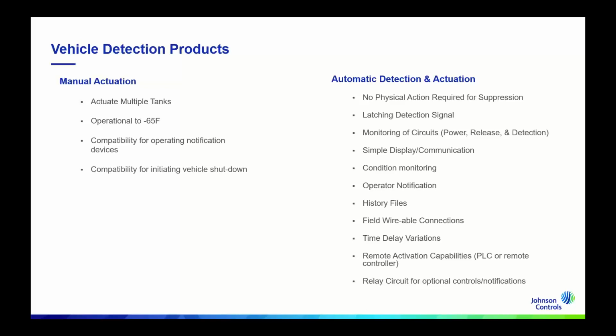In addition to the visual and audible indication to the operator, having the ability to access a history log within the system also provides valuable information about the system and the events that happen. In this case, that history log is basically the picture that can tell you 1,000 words. Automatic detection is critical in order for us to provide that holistic solution that doesn't require manual intervention by a human, right? So that, whether we're there or not, that fire suppression system is going to operate.